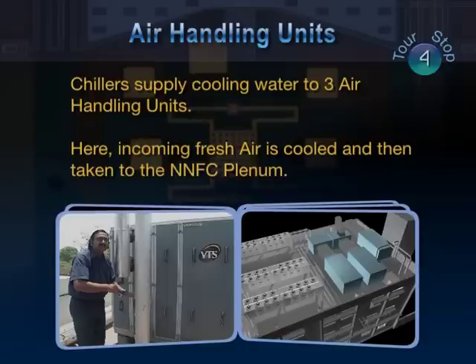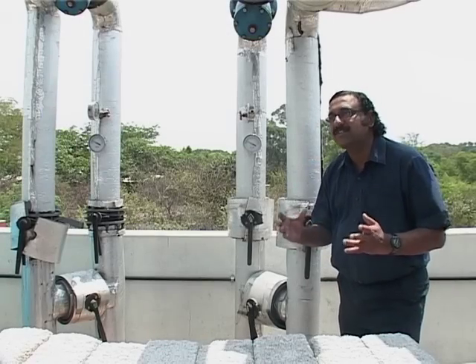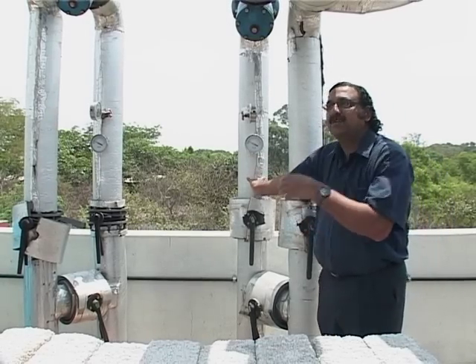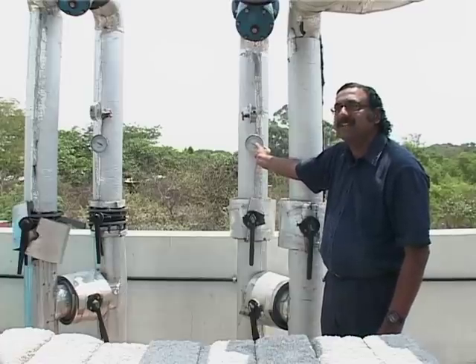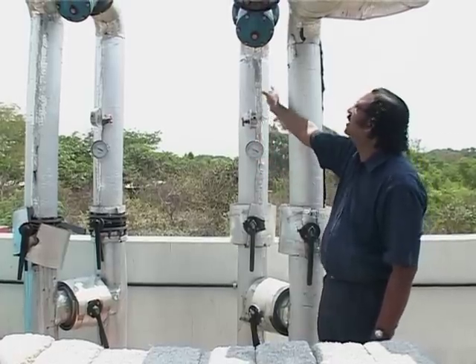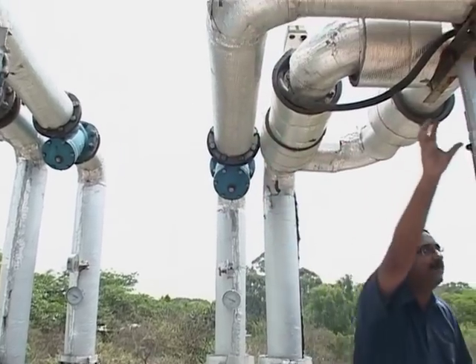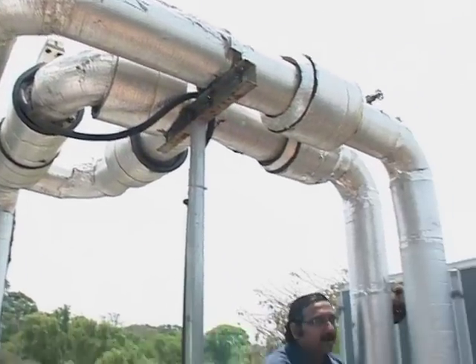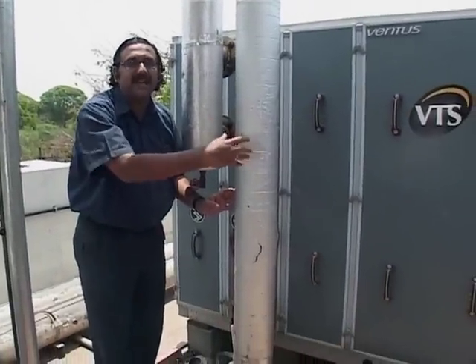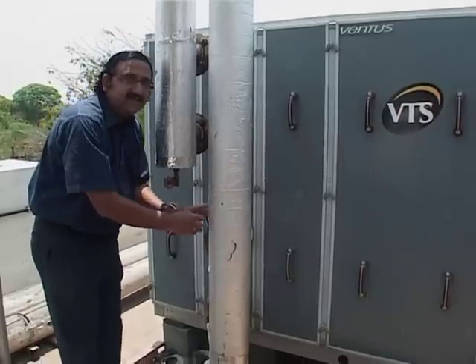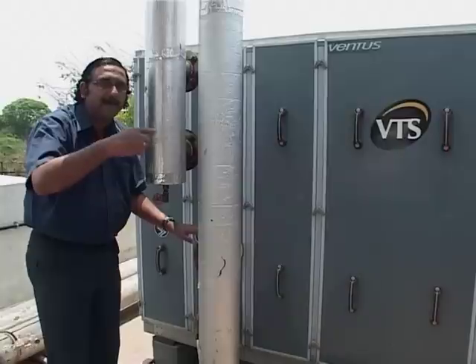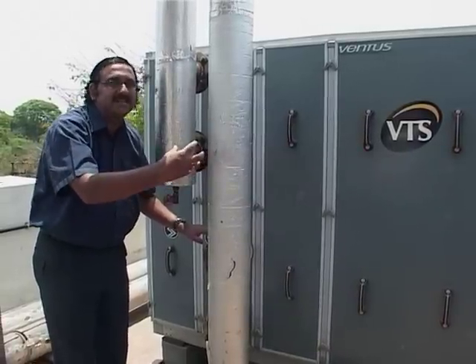The industrial chillers supply cooling water to 3 adjacent air handling units. Here, incoming fresh air is cooled with chilled water and then taken to the NNFC's plenum. The chilled water that is produced from the chiller unit is coming through this pipe to the air handling unit. The temperature of this chilled water is kept less than 10 degrees centigrade, and this water goes through this pipe, and it passes through this pipe and comes here, and it reaches the air handling unit. This is one of the 3 air handling units that we have in this facility. The chilled water that gets into this air handling unit is passed through a copper pipe, and that cools the air that is coming inside this air handling unit.